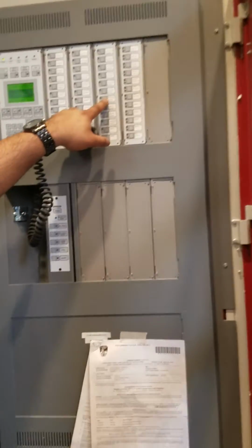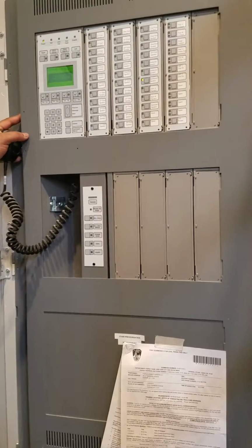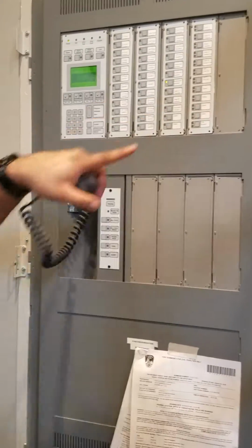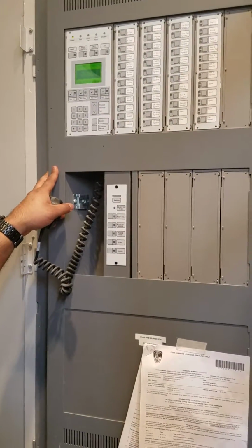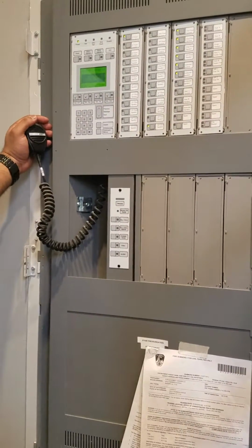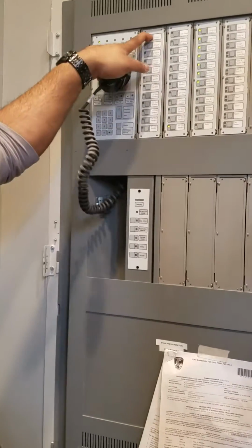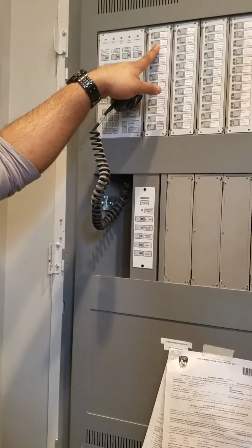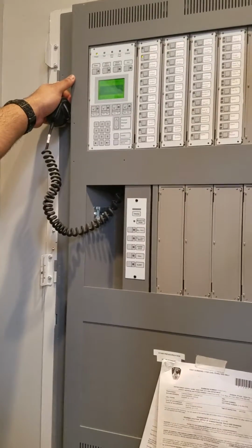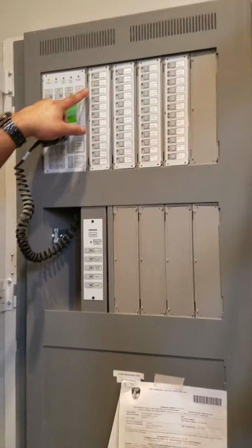Okay, let's try penthouse. Okay, so just the penthouse kicked on. Let's take that off. Let's try again. It's kind of weird. Try the 5th floor. See if it doesn't happen with that one. Doesn't happen with that. So the 3rd floor is connected to the 31st, 36th. It's not supposed to be that way.